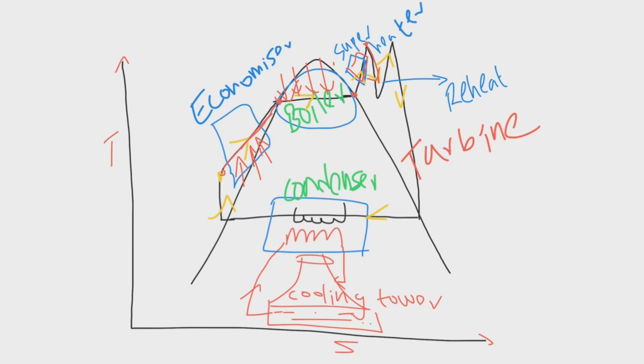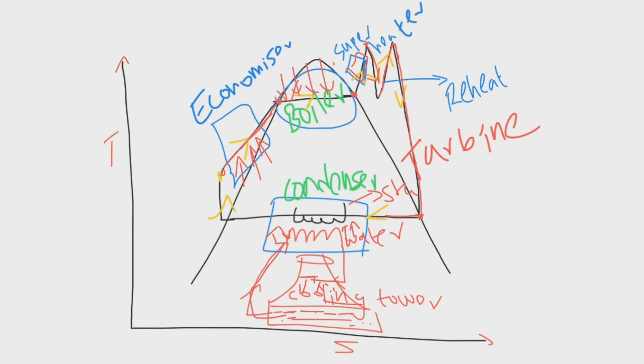To further increase turbine output, a reheater can be used after partial expansion. After full expansion, the steam exits the turbine and enters the condenser, where heat exchange occurs between the steam and cooling water. The water gets heated and exits at higher temperature, which is then sent to the cooling tower where spray nozzles and draught fans cool it down. This cooled water is supplied back to the condenser, and the feed water cycle repeats through the feed pump.